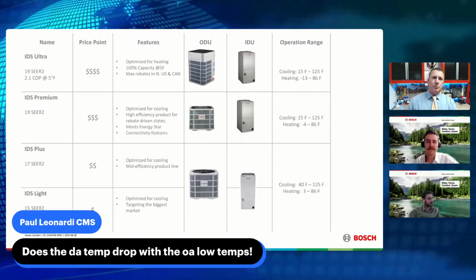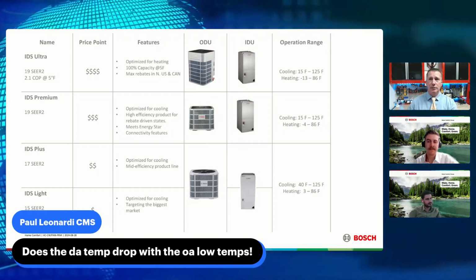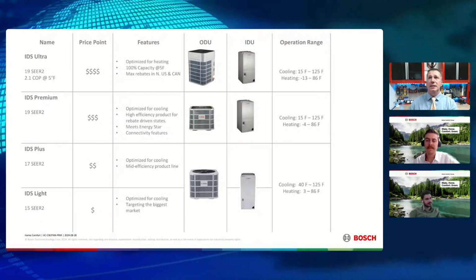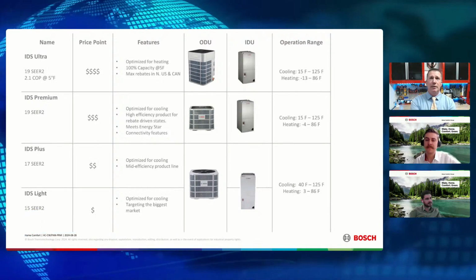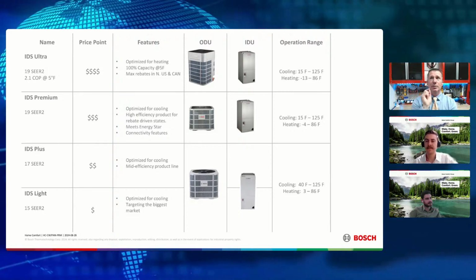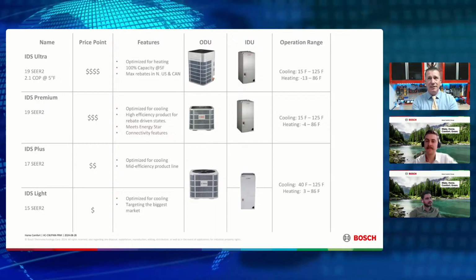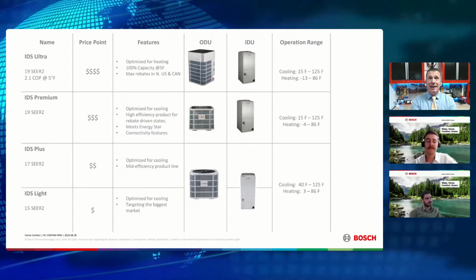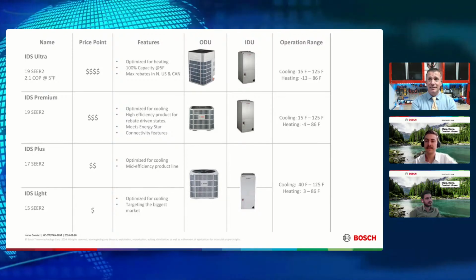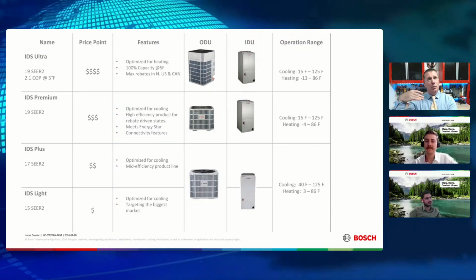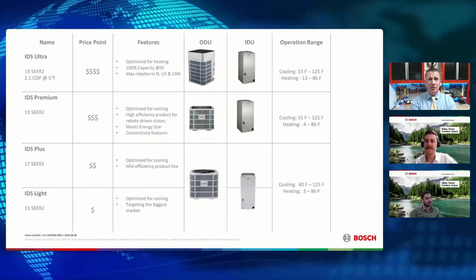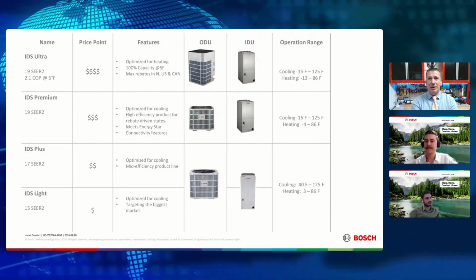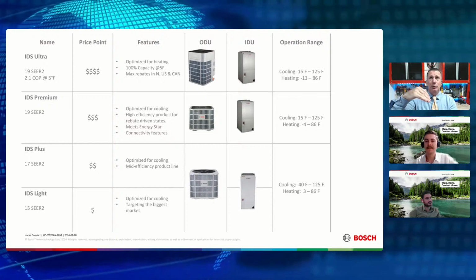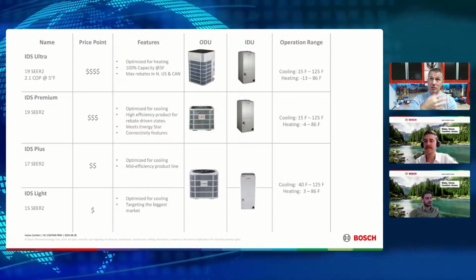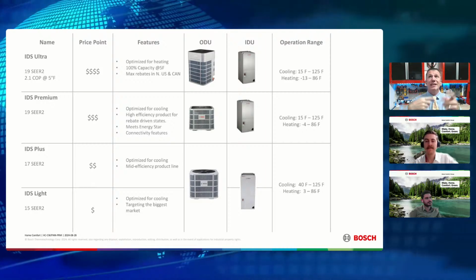Very good point, right? When we start seeing temp drops with the lower temps, absolutely. When you look at those charts, you'll see drops in BTU capacities as we start reducing. But the beauty of an inverter is that many of these inverters are not maxed out at heating capacity at 47 degrees, right? They're maxing out at heating capacity when they start getting down into the 10 degree and 5 degree range. Where we traditionally would think of a heat pump, especially a single stage or a two stage, when it's in heating, it's just maxed out. And so we continue to lose BTUs as the temperature drops because we don't have as many BTUs outside to transfer, right? Our compressor's at a fixed speed.